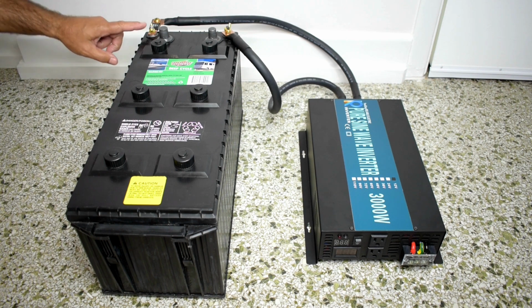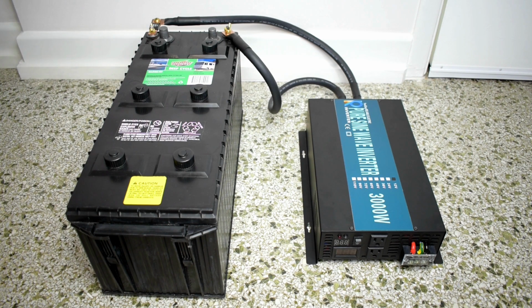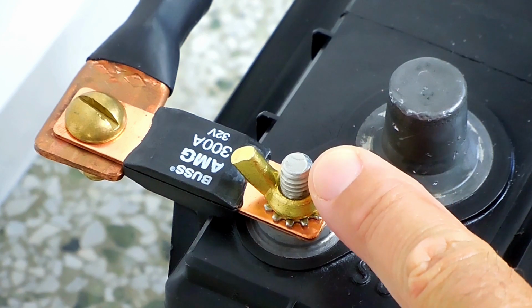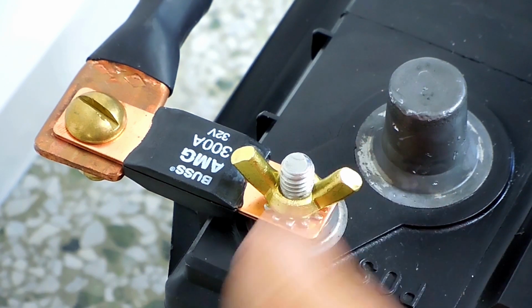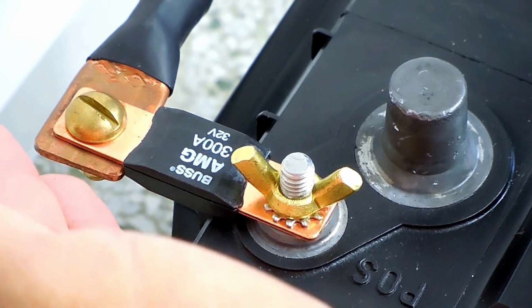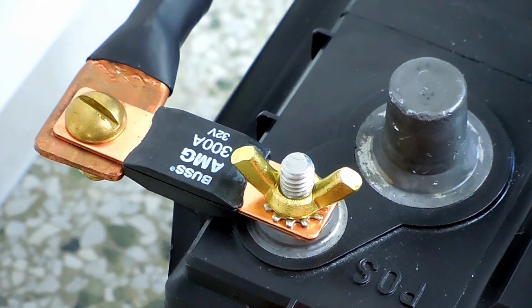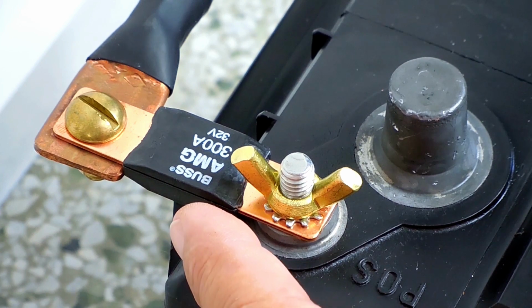Now take a look right over here up close. What you're looking at is a 300 amp 32 volt fuse, and you definitely want to have a fuse between the battery and the inverter. The inverter is 3000 watts, so you want to use around a 300 amp fuse.